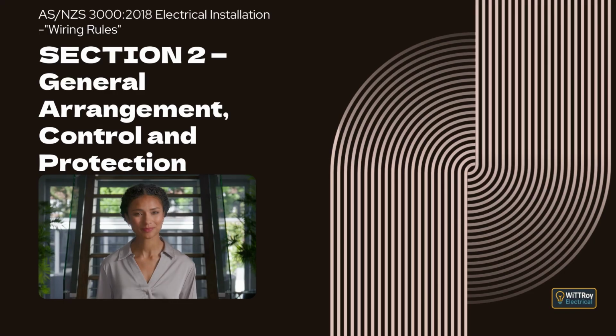The explanation also recognizes that other effects, such as mechanical stress, arcing energy, and forces caused by very high currents, may need to be considered, and this information is normally provided by manufacturers. The clause also explains that short-circuit currents must be cleared before a conductor reaches its maximum safe temperature, because excessive heating can damage the conductor or its insulation.